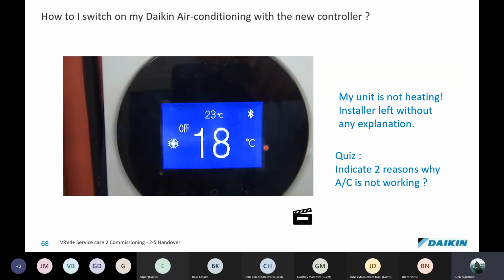So what's happening is that, first of all, the indoor fan will go off. What happens when that happens is that the compressor starts to pump hot gas through the indoor coil. And once that coil reaches a prescribed temperature, only then does the fan come on, and this is cold draft prevention. Now this might be perceived by an end user as a problem.